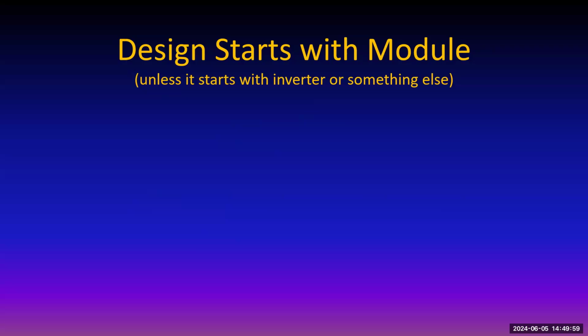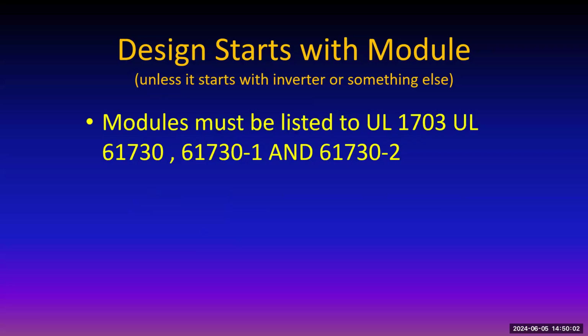Okay, so usually design starts with the module, but sometimes there's other reasons. But in any case, you got to have modules. So first thing is they need to be listed. Used to be UL 1703 would do the job, but the 61730 has gone into the international scene since modules are made all over the planet now. And so folks have gotten together and agreed that if you list it to UL 61730, which is actually a copy of an international standard, and if it's listed to that standard, it means it's pretty quality stuff. And that's like a UL listing of almost anything. It's highly likely that you need to have a UL listing or you're not going to be allowed to install it, whether it's an air conditioner or whatever it is.